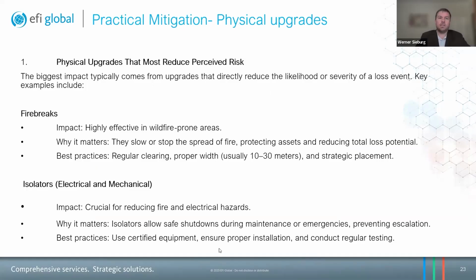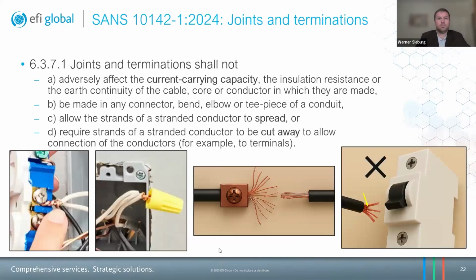Now, number C and D, sorry, just the previous two. Number C and D deal with basically the same thing, but you must not allow the strands of a stranded conductor to spread. And obviously the second from right picture is kind of grotesque in that regard. The conductors are very spread, and once you connect that with the right-hand side of the cable, there will not be sufficient contact between the two sides of the joint. And that'll also result in a loose connection, a hot connection, and in the end, it might result in a fire.